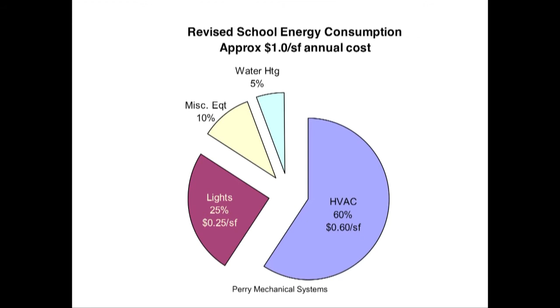So how else can we improve our energy consumption? Well, now you have to start looking at the HVAC components on an individual basis. If you look at a traditional ranking of systems as far as efficiency goes, your water-cooled chillers are typically the most efficient. Most buildings see a cost break point at about 500 tons for when you jump from air-cooled to water-cooled.